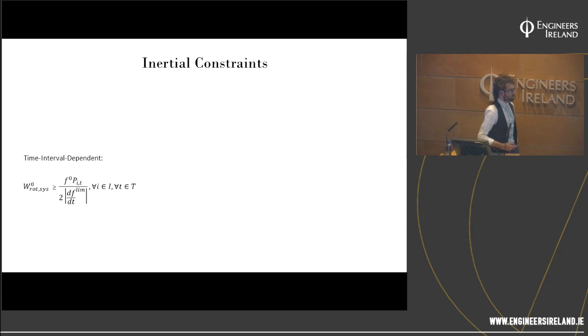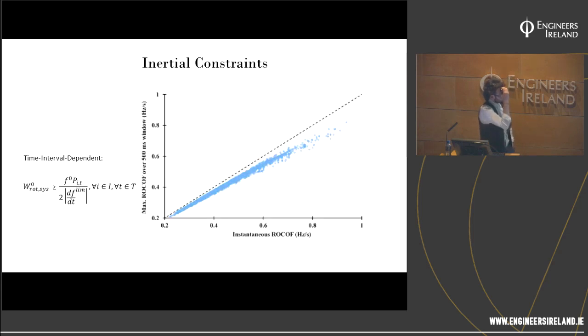Now the thing is that it changes with each time step. So at every point it will see, okay, what's my contingency? What do I need? And then it will optimally choose the binding contingency and the sum of the inertial provisions from the units to make sure that you're within the RoCoF limit that you set. The really nice thing about this constraint is it's a linear approximation.